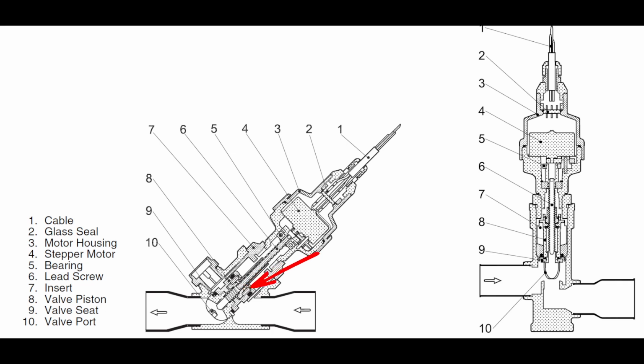Why they go that path, I think it has to do with trying to prevent it getting in a bind. Even if something weird happens and the threads have an issue, that Teflon will kind of reform and shape itself in a way where it can still be more reliable, more functional. Whereas if this was steel on steel, and let's say something got a burr or something weird happened, well, that steel is going to lock up, and these motors aren't that strong. So that steel gets in a bind, this motor may not be able to break it free. So your failure rate would probably go far higher than having that steel on with a Teflon thread.